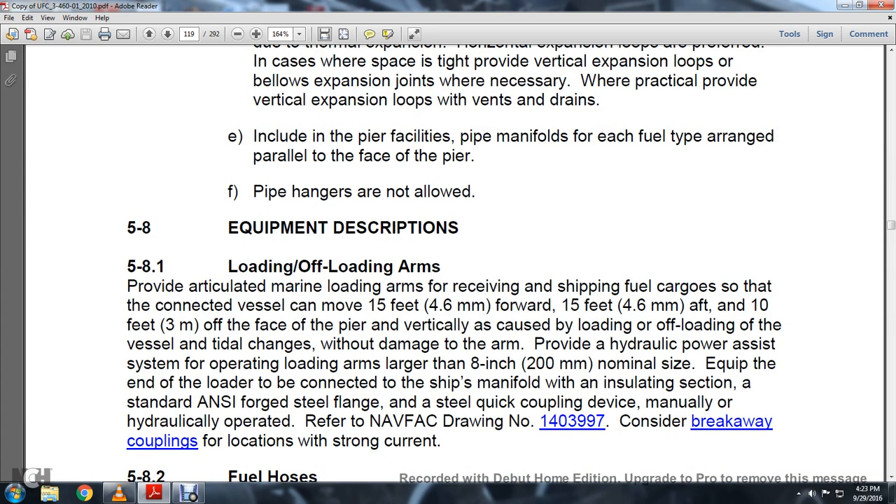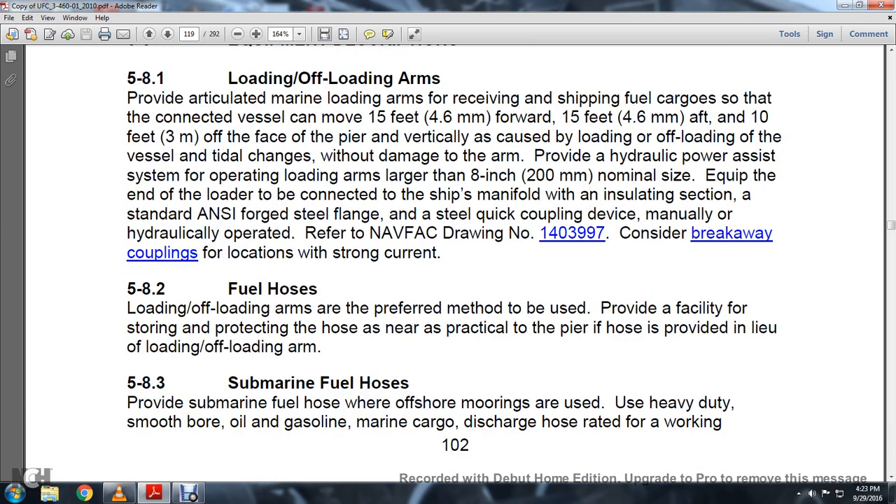Section 5.8 Equipment. Section 5.8.1 Loading and Offloading Arms: Use articulated marine loading arms for receiving and shipping fuel cargo so that the connected vessel can move 15 feet forward and 15 feet aft and 10 feet off the face of the pier vertically, as caused by loading and offloading, without damage to the arm. Provide hydraulic power-assist systems for operating loading arms larger than 8-inch nominal size. Equip the end of the loader connected to the ship manifold with an insulation section, standard ANSI forged steel flange, and a manual hydraulic-operated device complying with NAVFAC Drawing No. 1403997. Consider breakaway couplings for locations with strong currents.